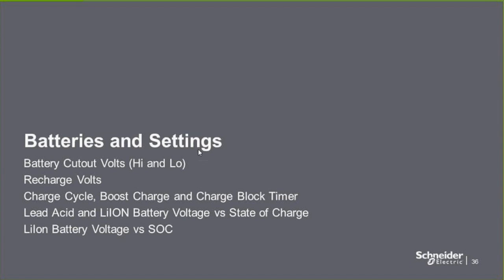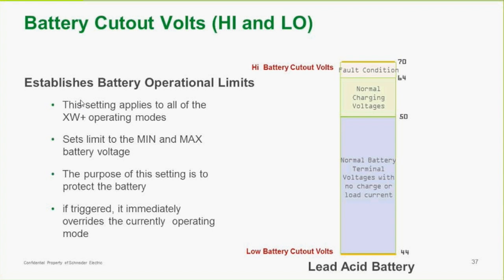So let's talk about the batteries and settings. There's a number of settings that are associated with batteries. Battery cutout volts, high and low, establish battery operational limits. This little chart on the side talks about voltage settings. We have a low voltage cutoff. If the inverter actually reaches that and there's no AC coming in, it will shut down. So we don't want that to happen.